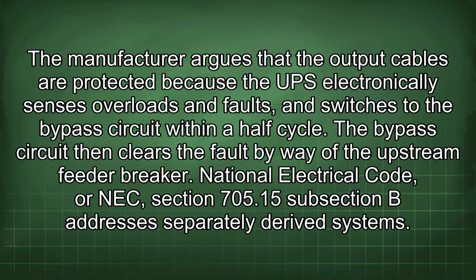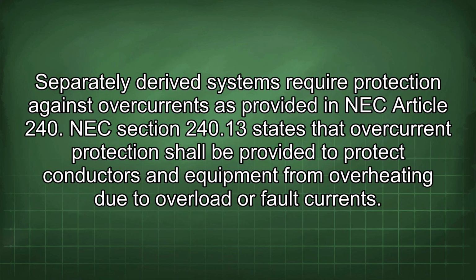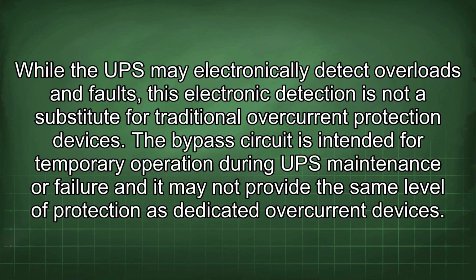National Electrical Code, or NEC, Section 705.15 subsection B addresses separately derived systems. Separately derived systems require protection against overcurrents as provided in NEC Article 240. NEC Section 240.13 states that overcurrent protection shall be provided to protect conductors and equipment from overheating due to overload or fault currents. While the UPS may electronically detect overloads and faults, this electronic detection is not a substitute for traditional overcurrent protection devices. The bypass circuit is intended for temporary operation during the UPS maintenance or failure, and it may not provide the same level of protection as dedicated overcurrent devices.